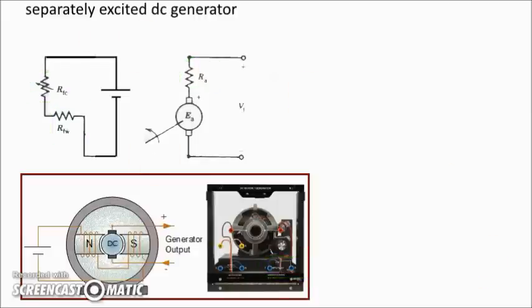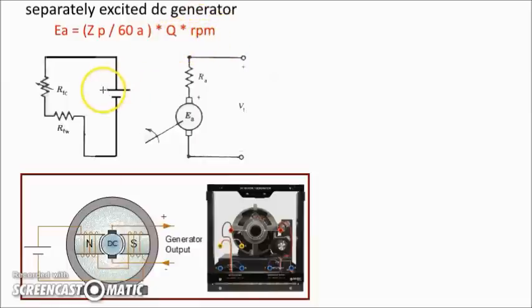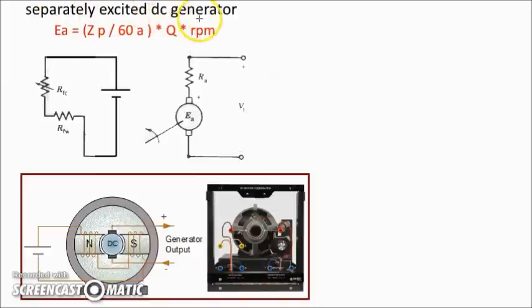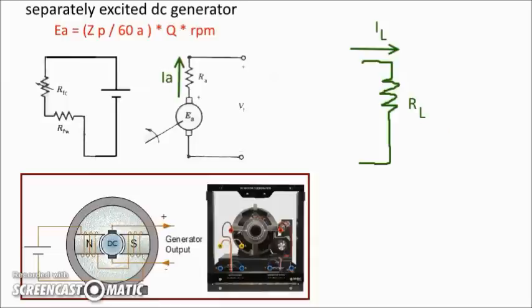The armature voltage follows this equation: Ea = k × φ × RPM. If we maintain a fixed speed for the prime mover and ensure that the external power supply and rheostat resistance don't change during measurements, that means our flux φ will remain the same. Because of this equation, in a separately excited DC generator Ea must be constant.